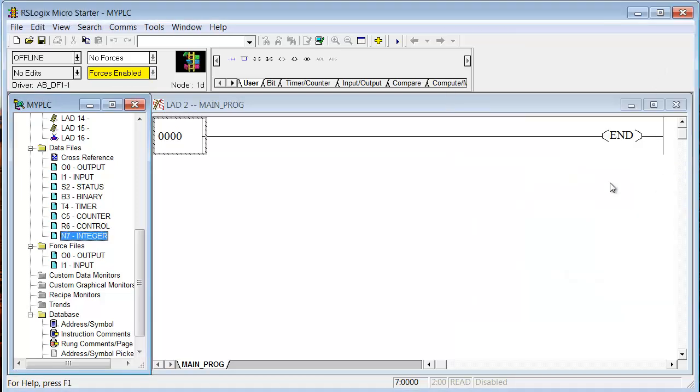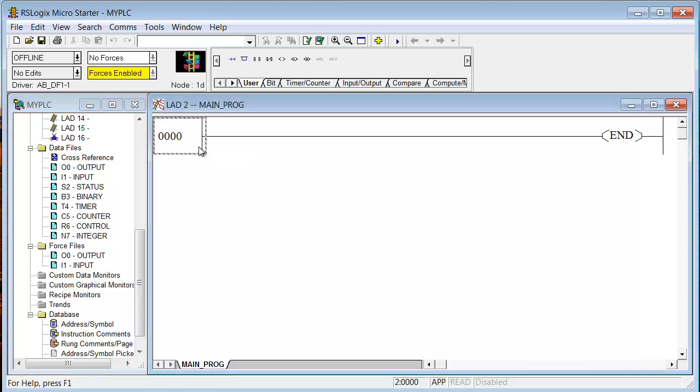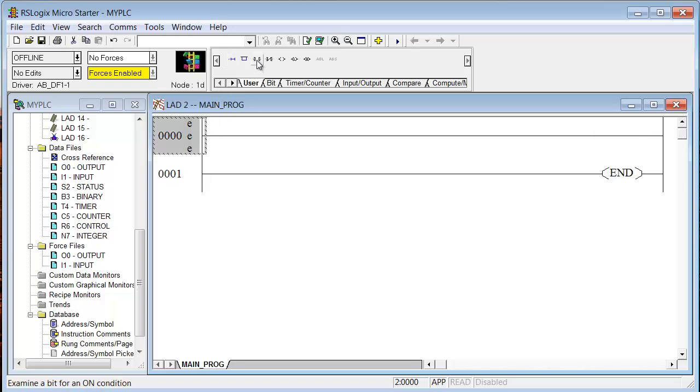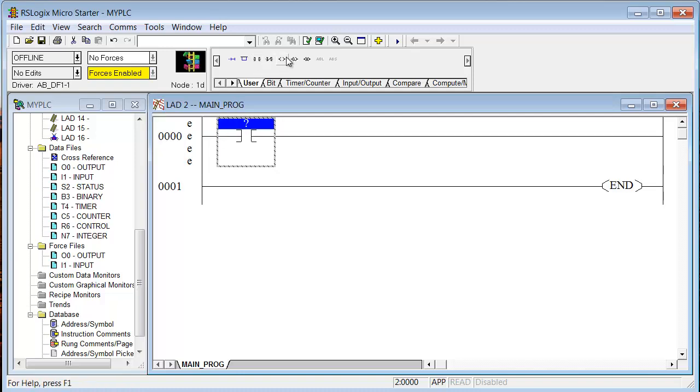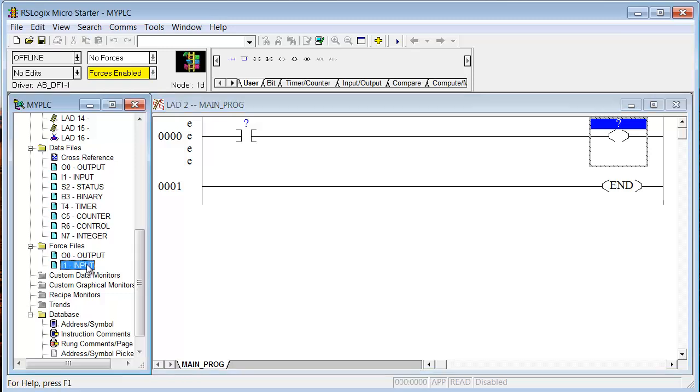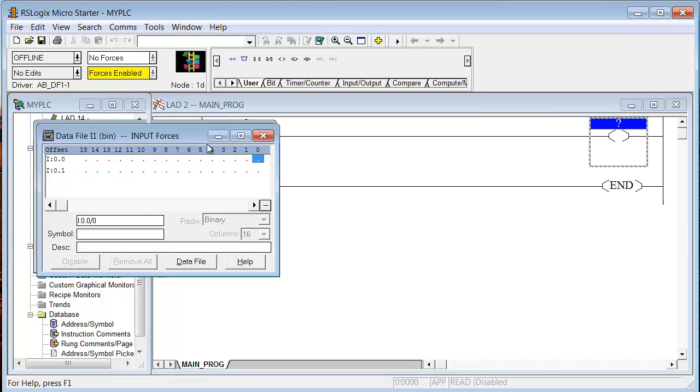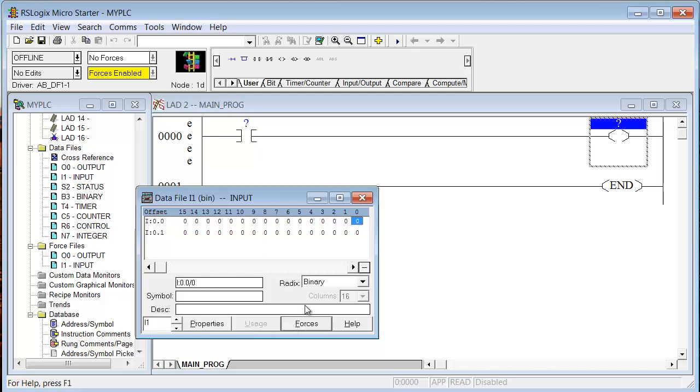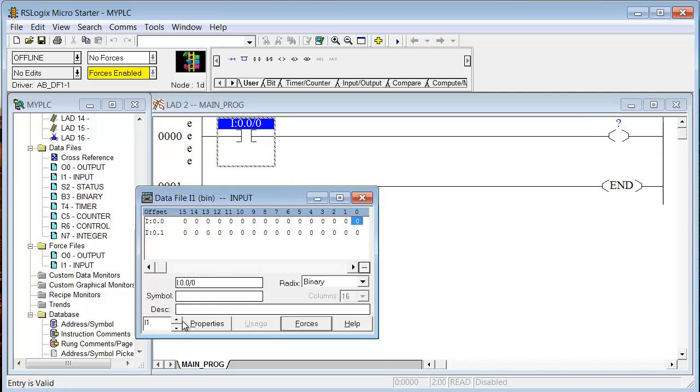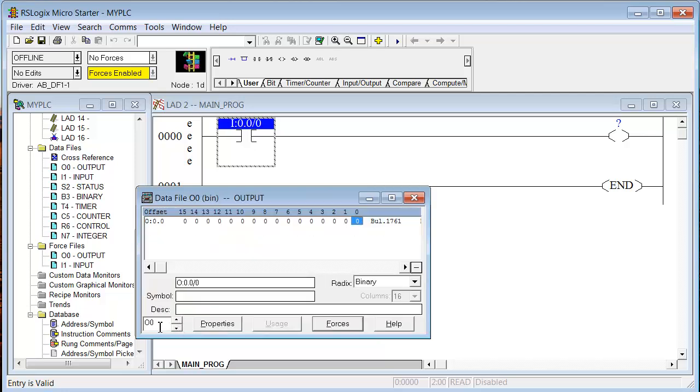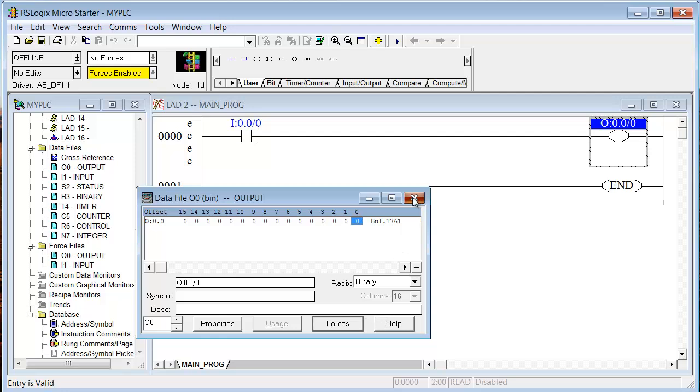I'm going to close those down, and I'm going to create one rung of logic. Now, this presentation is not on programming. It's on navigating. But we want to create something so we can download and go online. So I'm going to drag a rung down, drag an examine if on down, drag a energized output down. And there's several ways that you can use these instructions to address memory. I could just type in the address, or I can open the input file like this and drag the address over. You want to make sure you have data file selected and not force. I can drag it over, and then here you see it says I1, S2, I1, output 0. So I can grab an output address and drag it over here. Or I could have just typed them in.